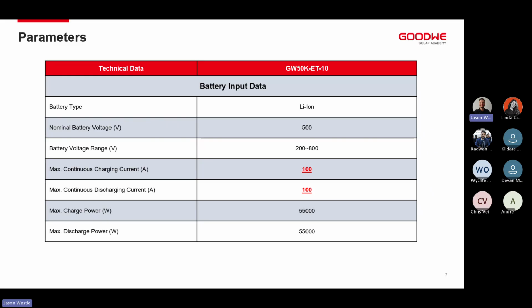If we look at the battery input data on the ET50, you'll see it is a high voltage inverter, meaning you need to use high voltage batteries, with the maximum charge and discharge currents of the battery input port being 100 amps. We can continuously charge and discharge this inverter at 55 kilowatts, 55,000 watts. Again, this is very much dependent on the batteries that we have installed. If we're installing batteries that can't discharge at 100 amps or can't discharge at 55 kilowatts, we're obviously not going to get that full amount out.